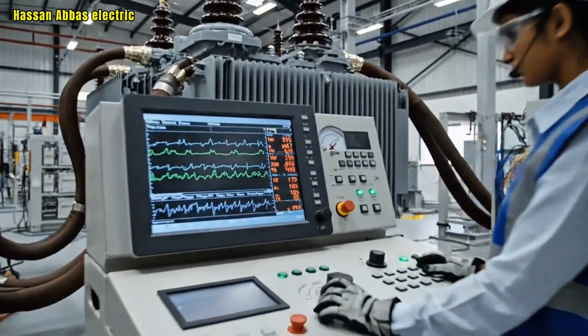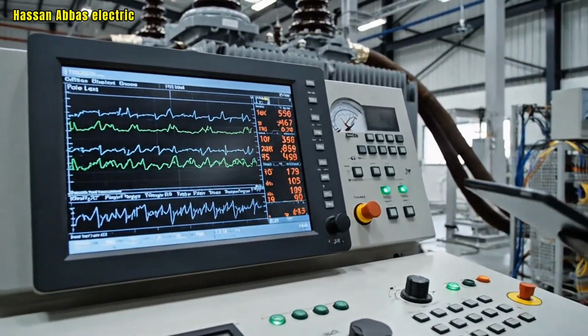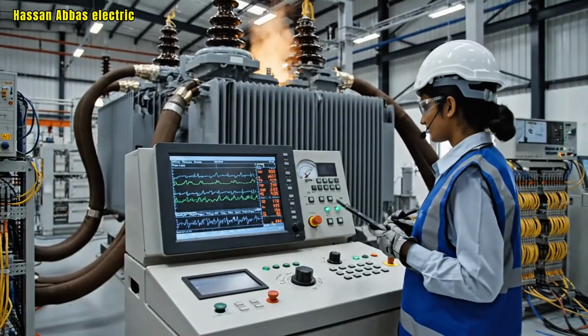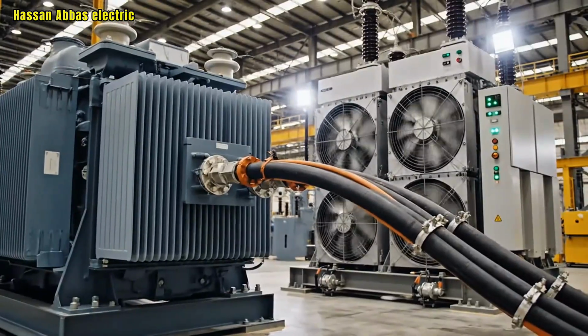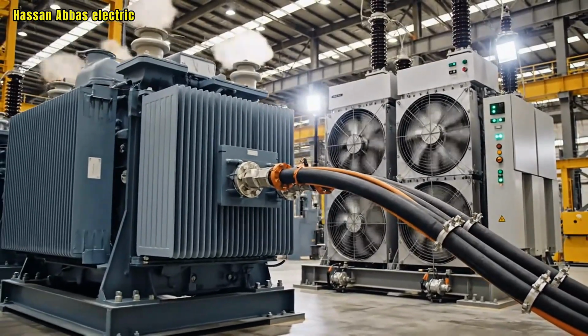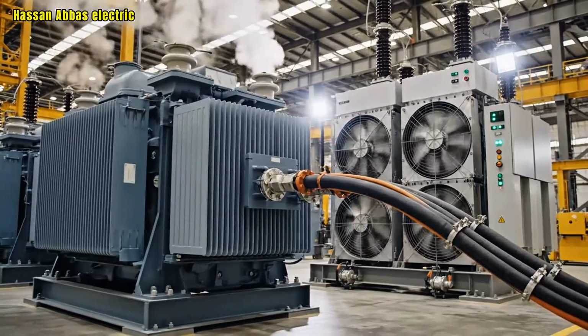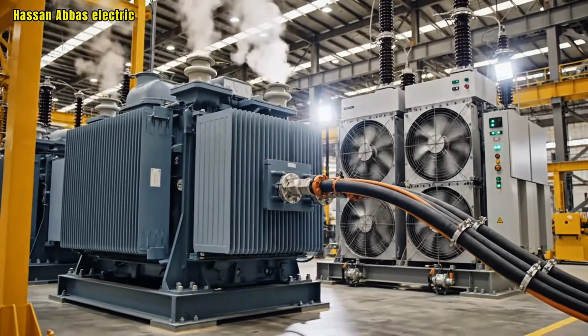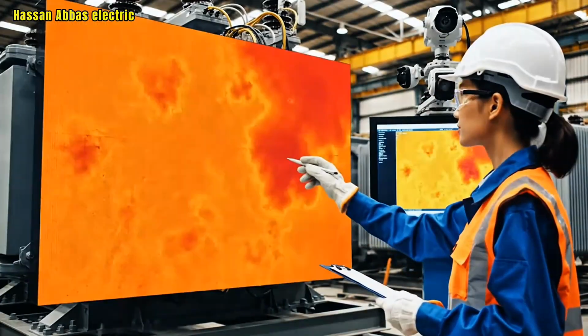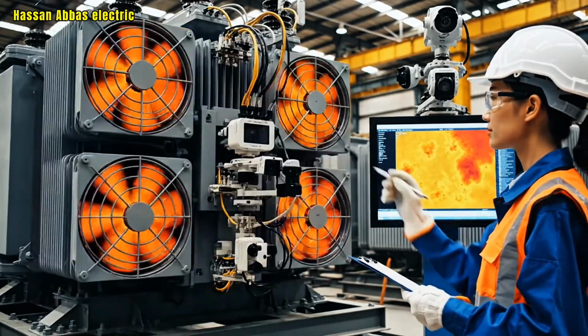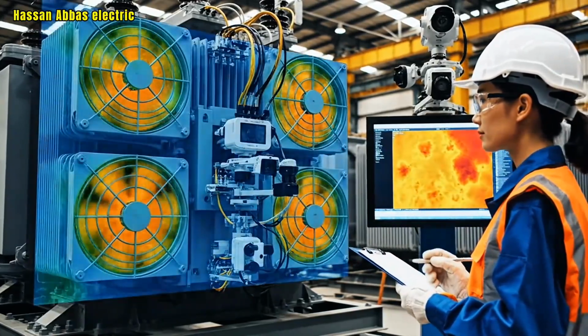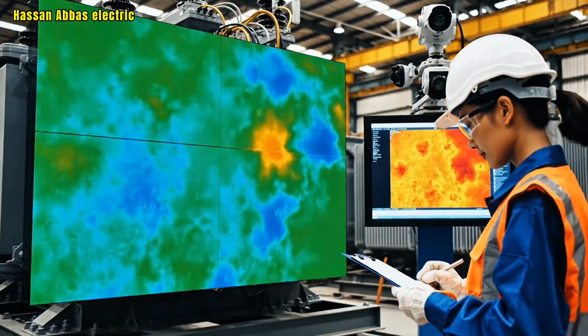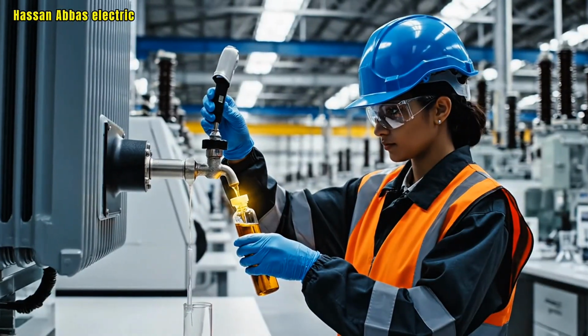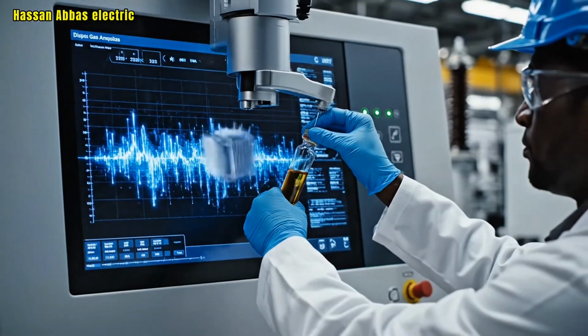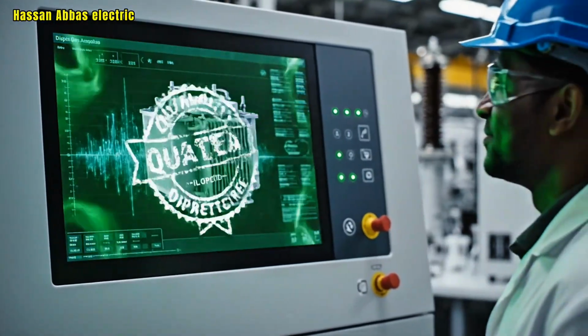No load loss testing measures energy efficiency of the core. The transformer is tested under simulated load conditions. Temperature rise is monitored to verify cooling efficiency. Insulating oil is tested to ensure long-term reliability.